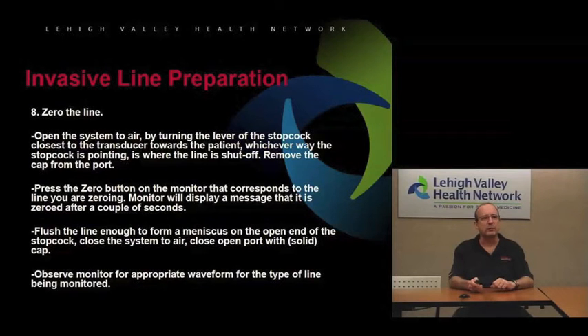Once you have it shut off towards the patient, then you can remove the cap from the port. Press the 0 button on the monitor to correspond to the line you are zeroing. That monitor will display a message that it is zeroed after a couple of seconds. And then you flush the line to form a meniscus again on the open end of the stopcock. Close the system there, then put the cap on. And it should be a solid cap, especially at that point.